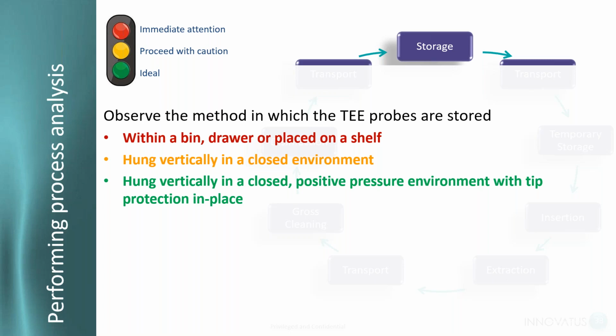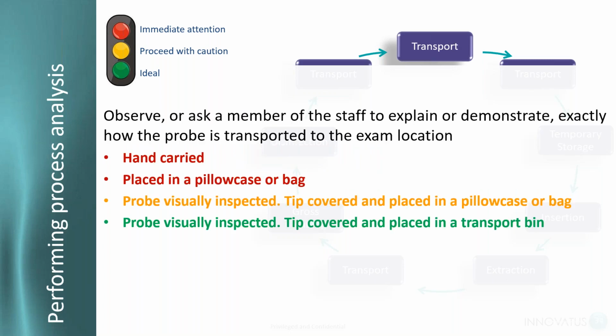Positive pressure is ideal because these probes are stored in these cabinets post-disinfection, typically. We want positive pressure with a HEPA filter on there, so we're not getting contaminants within that cabinet. So transport: how are we transporting probes? Again, this is where a lot of our trauma occurs. So hand-carried probes, not a good idea. Pillowcases and bags, definitely not a good idea.